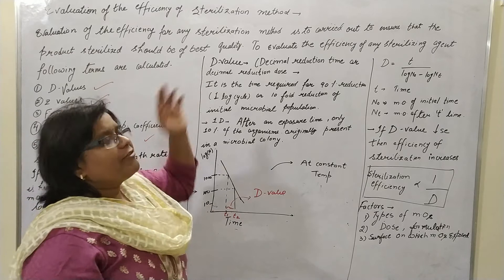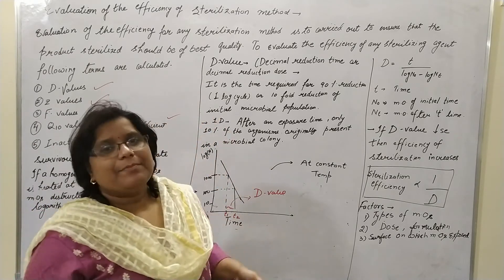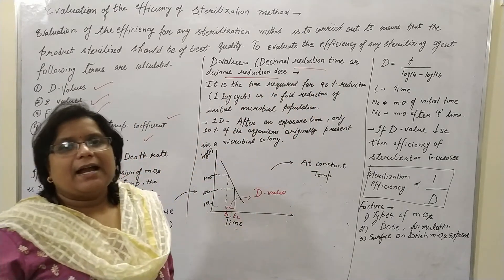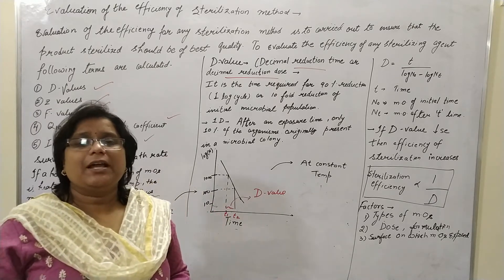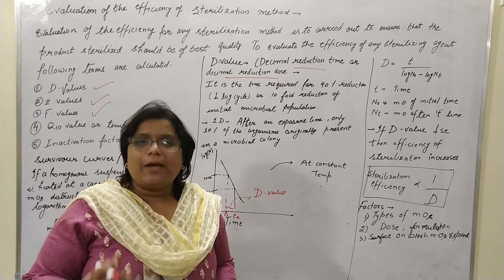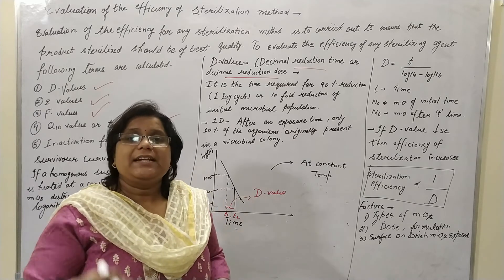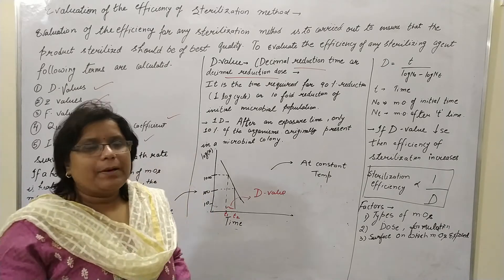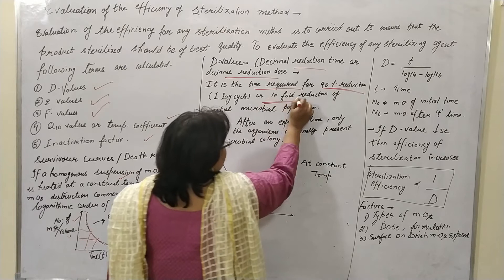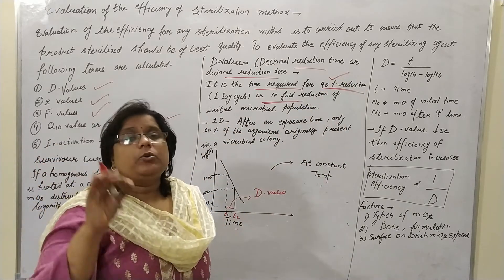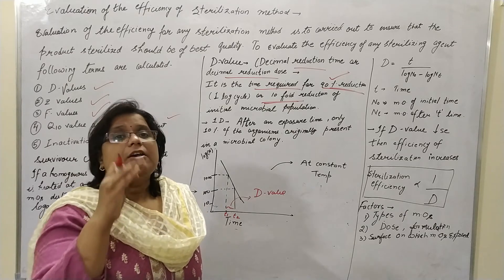Now we will discuss about the first value, that is the D value. We will discuss the survival curve of the death rate and the decimal reduction dose. The main thing is — it is very simple — because if we are introducing 90% reduction, the number of microorganisms decreases exponentially. This graph is known as the exponential graph or the survival curve.